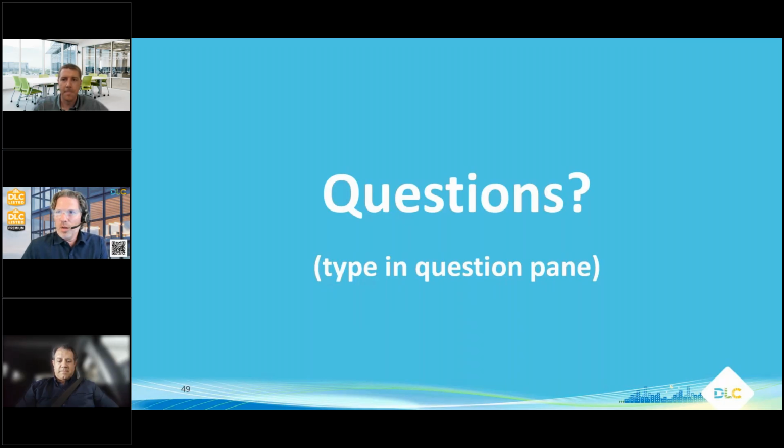Great. I'm going to say one. So, a question of what are some different ways to estimate savings? Typically I would suggest going to one of those technical reference manuals that we spoke about briefly earlier. TRMs are usually state or region level public documents that describe energy efficiency measures across all sorts of areas, from lighting to refrigeration to all sorts of things. And many of them include, or are based on research that includes, savings claims for specific measures.